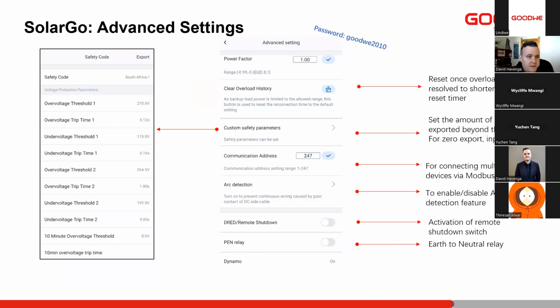So then we have the advanced settings. In the advanced settings, we've got a few more things. You'll see the power factor, clear overload history, things like that. Power factor, typically we do not touch, especially in domestic applications. When we have commercial applications, we can adjust the power factor if need be. Sometimes when the power factor on a commercial site is bad, we can adjust this to improve the site's power factor. And that can also reduce their bill, because when you have a lot of reactive power, an inverter producing at a nice 1 positive power factor can actually make the site's power factor worse.